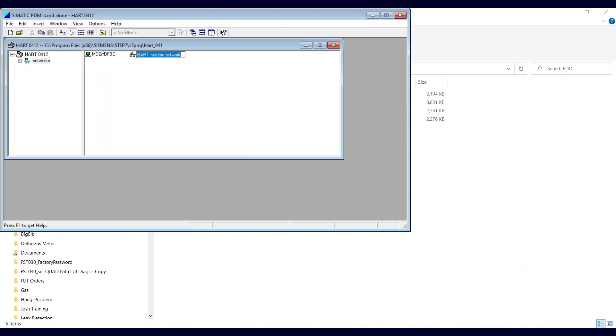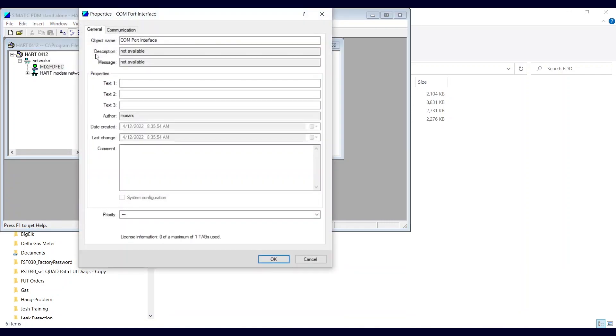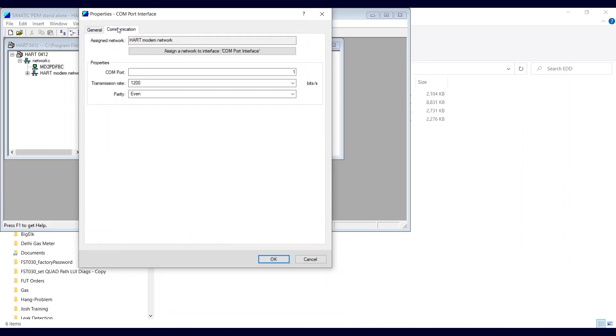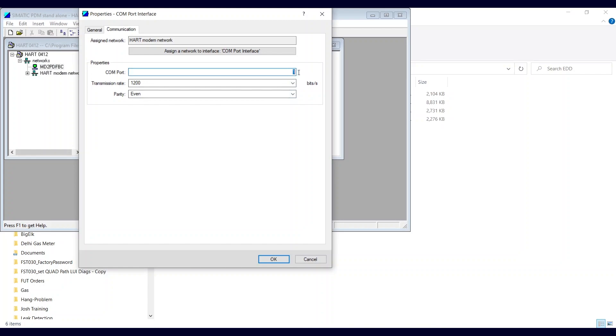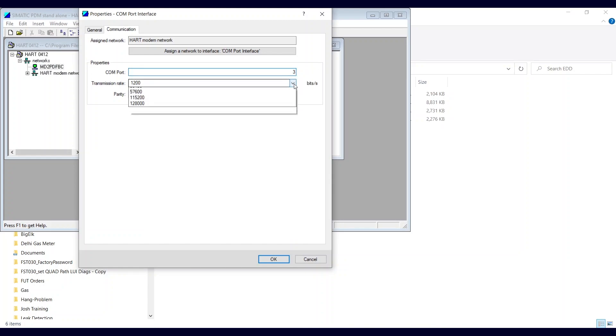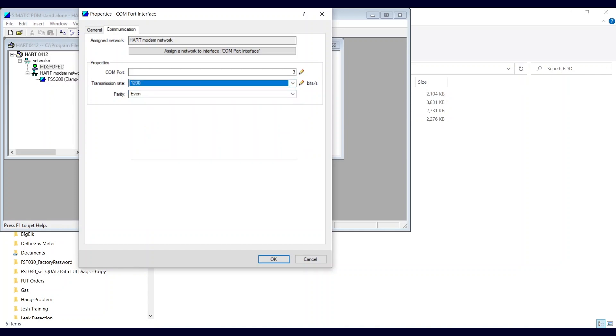Now we have a new icon — this is the PC. Double-click. COM Port interface — double-click. You have to find which port on your device manager. I see my Viator HART modem is on COM3, so I can change this. I think the baud rate only goes up to 1,200 — that's the transmission rate. The parity doesn't seem to matter.